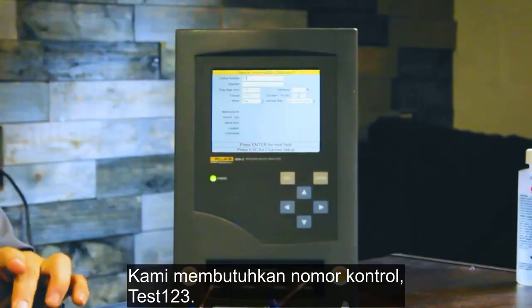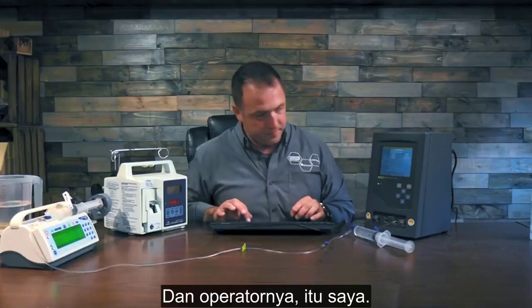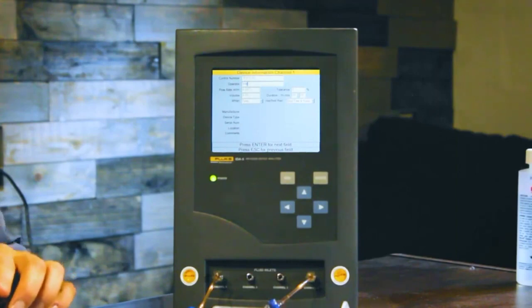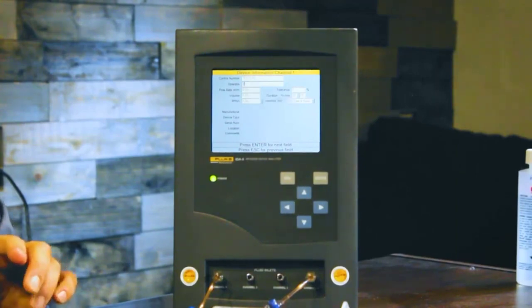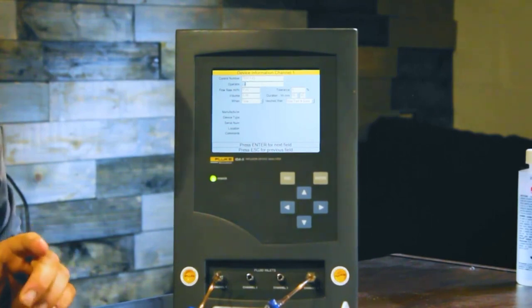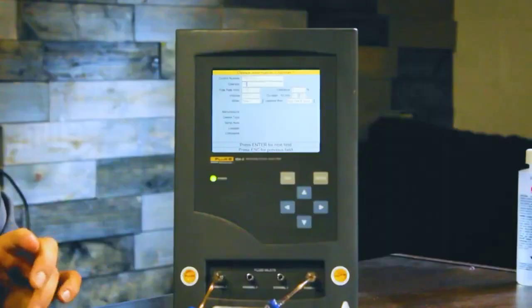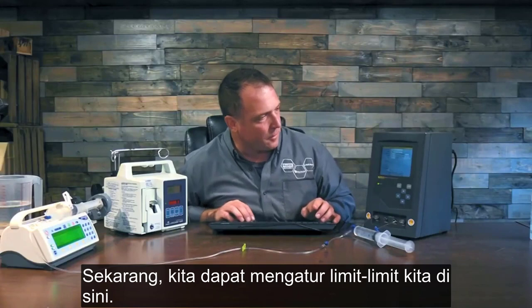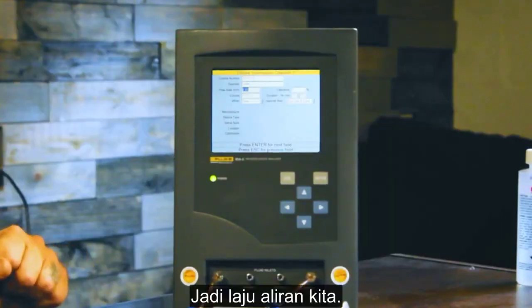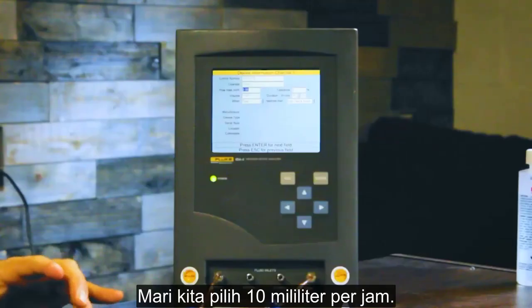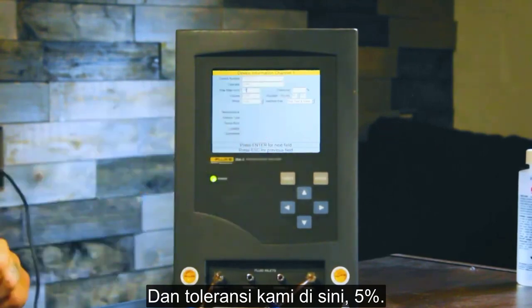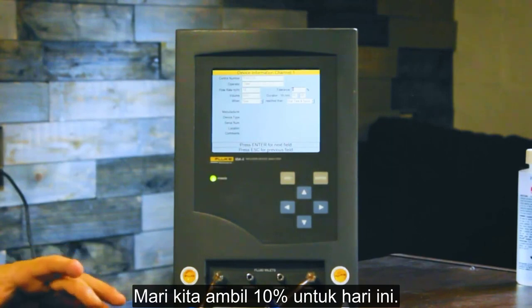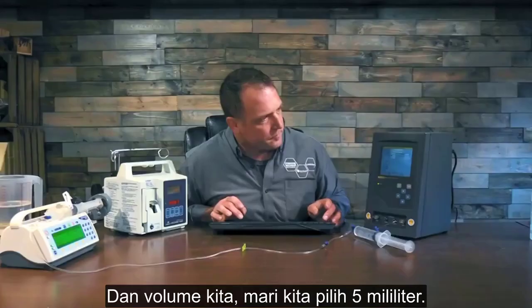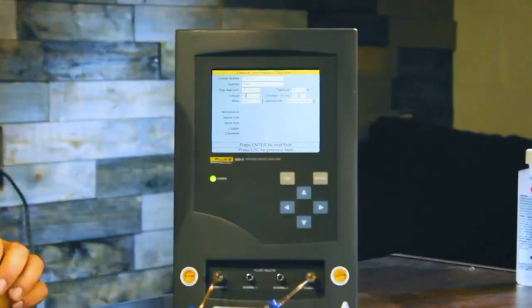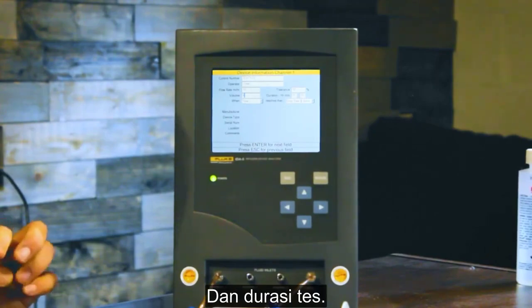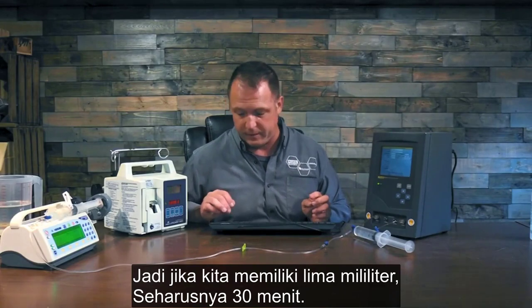We'll need the control number, test, 1, 2, 3. And the operator, that's me. I got big fingers this morning apparently. There we go. Now we can set up our limits in here. So our flow rate, let's just pick 10 milliliters an hour. And our tolerance right here, 5%. We can modify that. Enter. Tolerance, leave it at, let's take it to 10% for today. And our volume, let's do 5 milliliters. Not 55, 5. And the duration of the test, so if we have 5 milliliters, it should be 30 minutes.